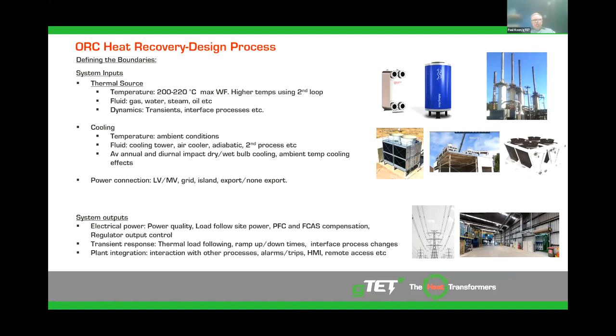So in order to investigate a heat recovery opportunity using ORC, we must first define the boundary conditions into the ORC system. So primary inputs include the thermal source, where we need to identify the temperature, the fluid, and the dynamics of that source. A secondary loop may be used to parallel multiple heat sources or heat sources that exceed the working fluid conditions. The dynamics are often challenging where interfaces have rapid transients or the ORC is used to load level the resource.